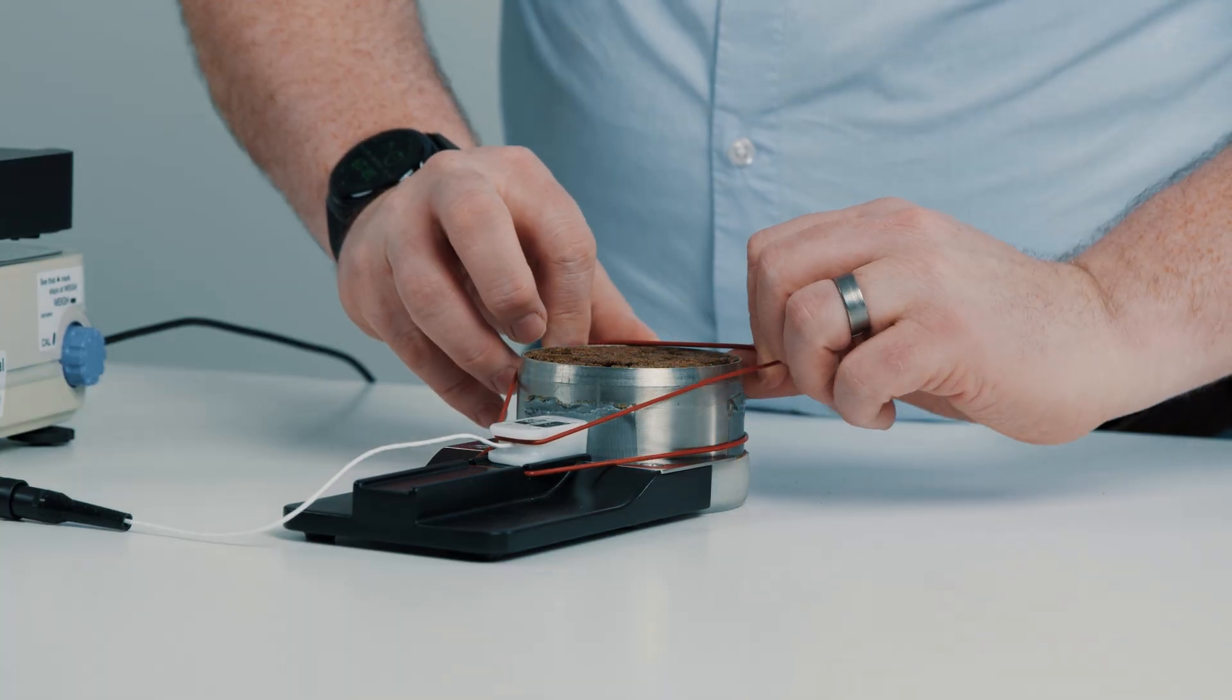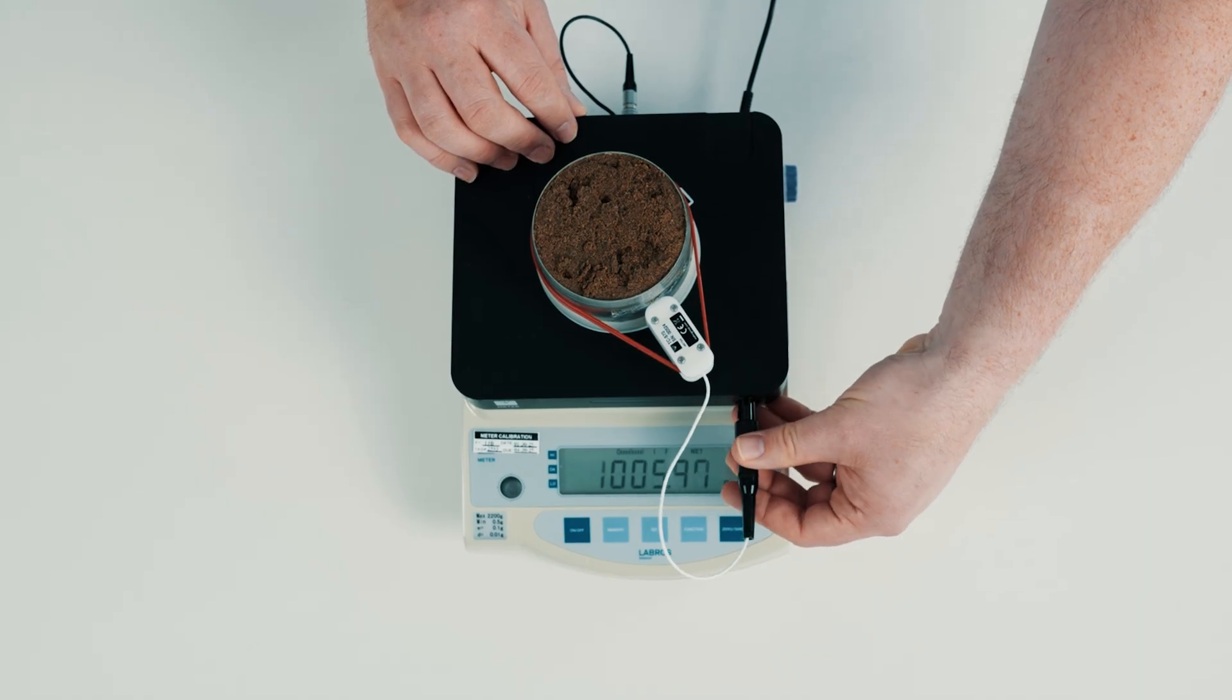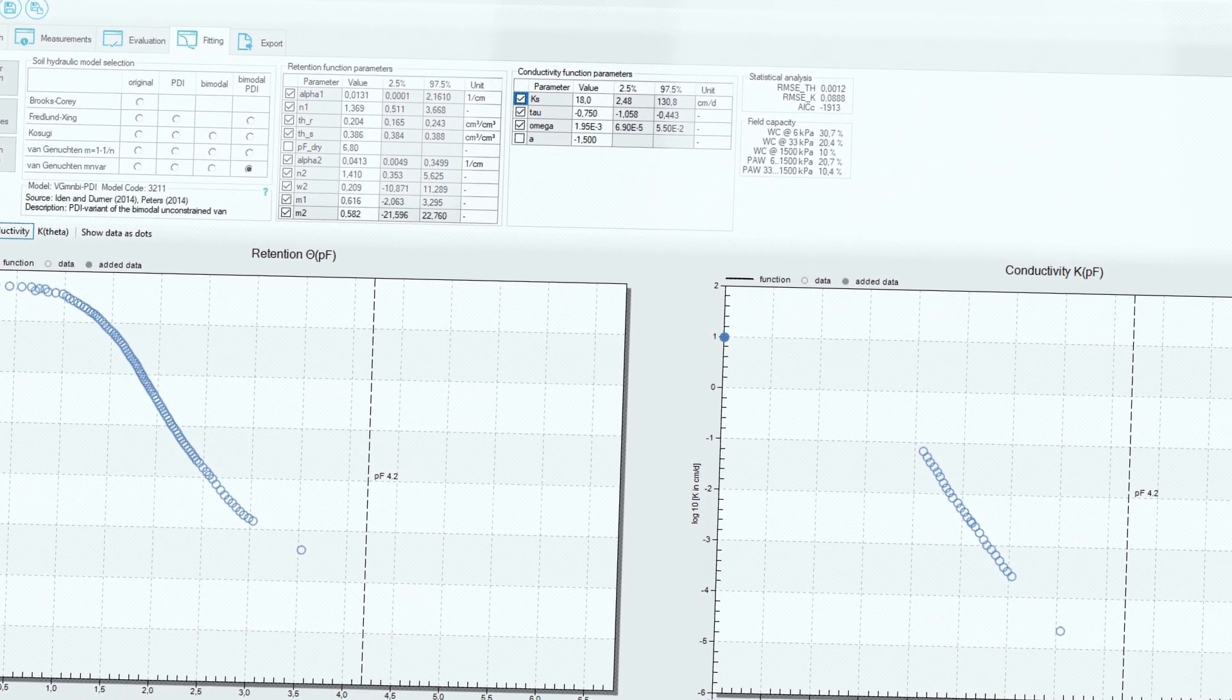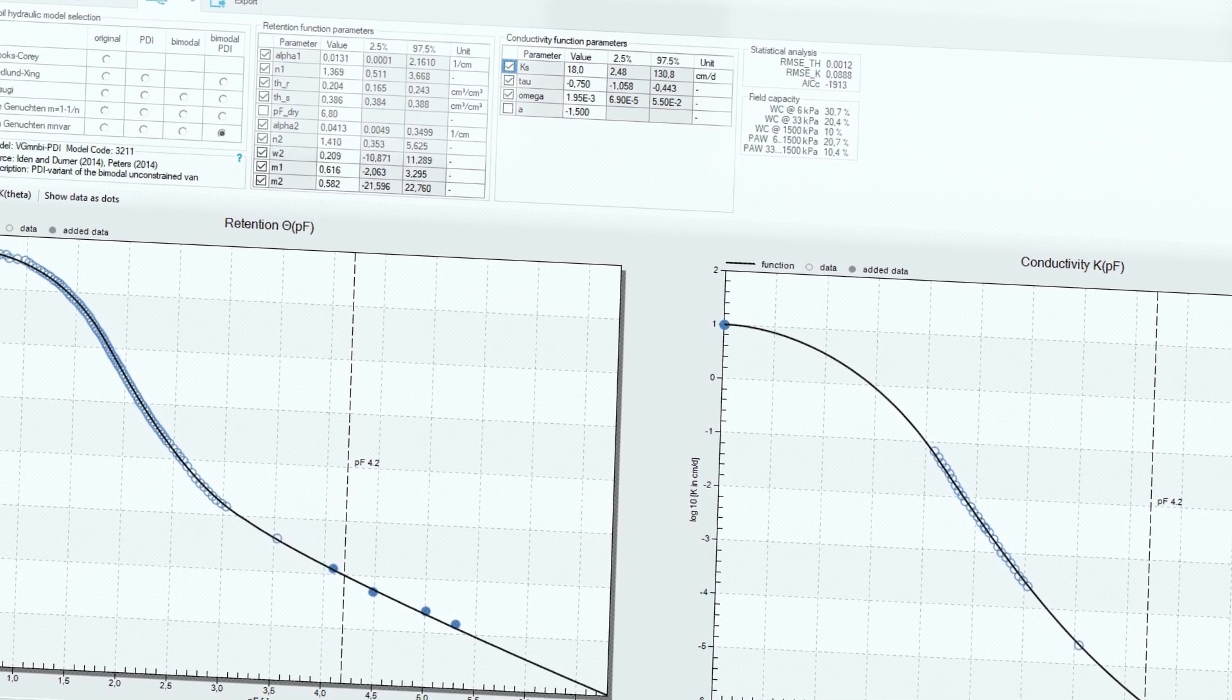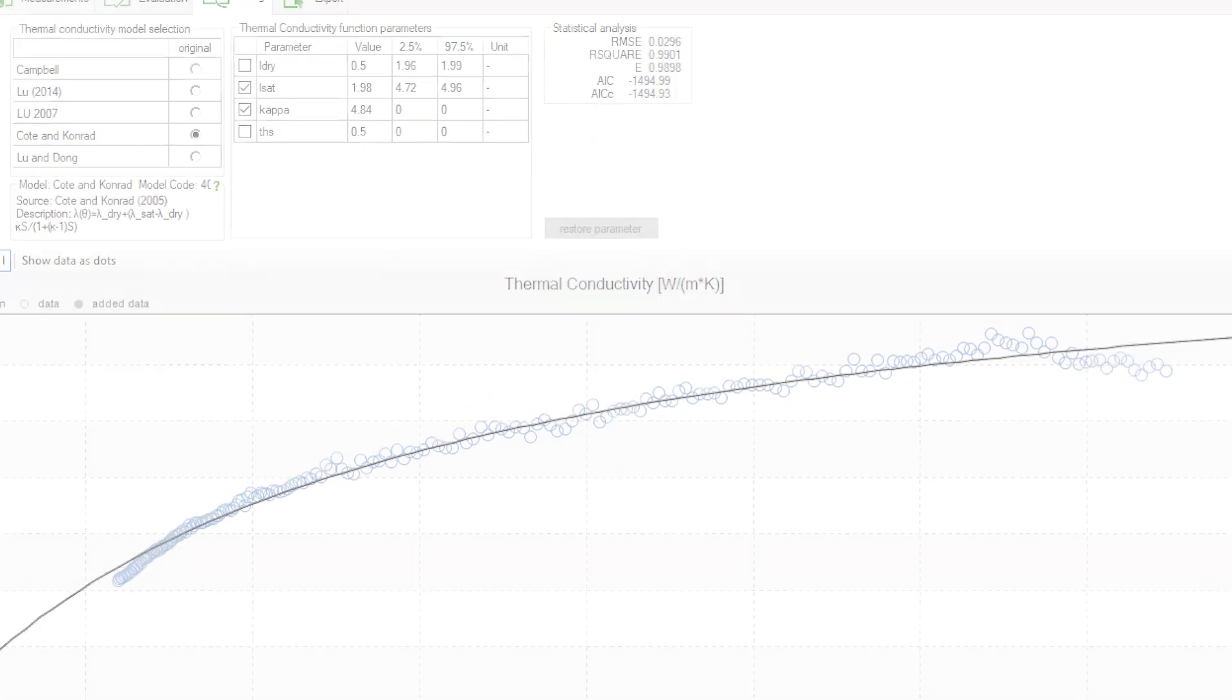Which is why when we test the sand, we want to test the entire relationship of water content to thermal conductivity to see what is the thermal conductivity of the sand in its saturated state all the way down to its oven dried state. And you need these two thermal conductivity values in order to do your thermal design.